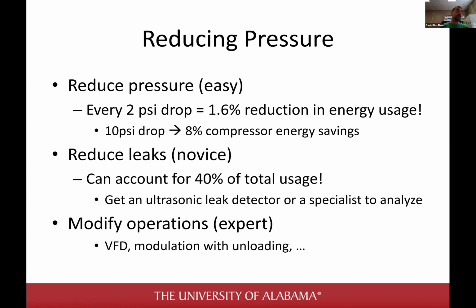What I usually recommend is that the plant manager goes up to the air compressor and goes down by 1 psi and waits for a week. And if no one notices anything, then why not do another psi? And then just keep doing that until someone at the back of the plant who's using the grinding wheel says, hey, this isn't working. Then you bump it up a couple of psi, and that's, I think, the best you can do at that point in terms of something that's very easy to accomplish. And we'll get into some actual numbers later, but reducing pressure is pretty easy.